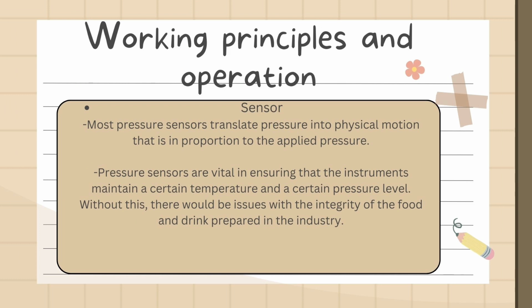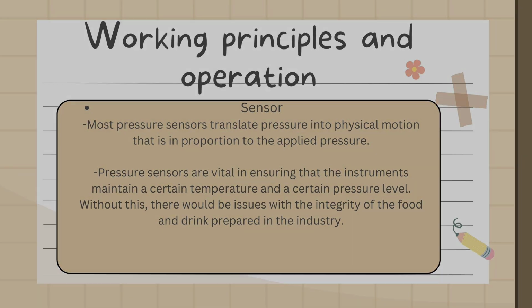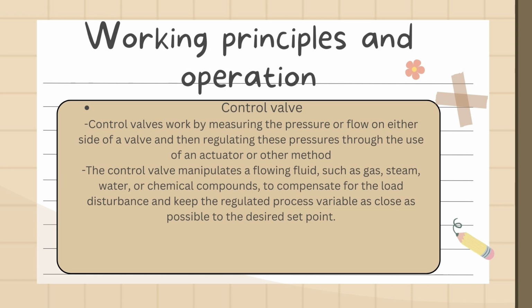Next is the working principles and operation of the sensor in pressure measurement control in the food industry. Most pressure sensors translate pressure into physical motion that is in proportion to the applied pressure. Pressure sensors are vital in ensuring that the instruments maintain a certain temperature and a certain pressure level. Without this, there would be issues with the integrity of the food and drink prepared in the industry. So next is the control valve.